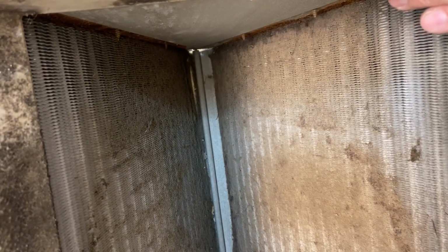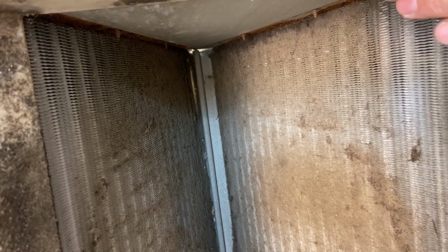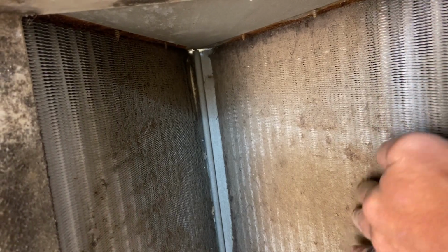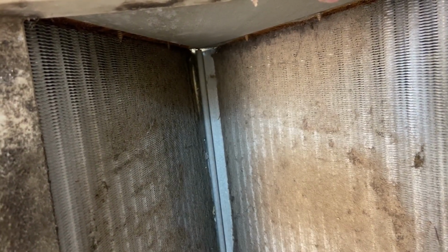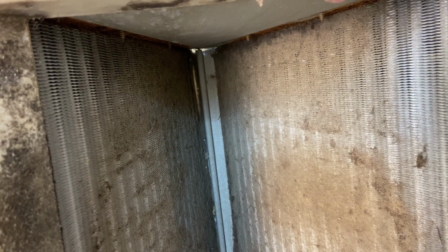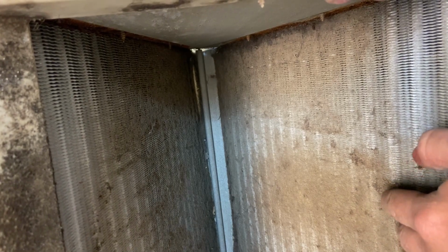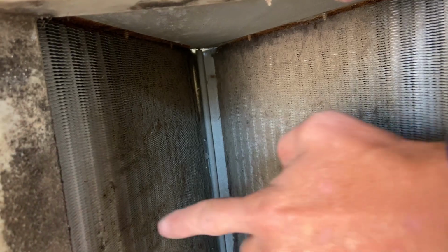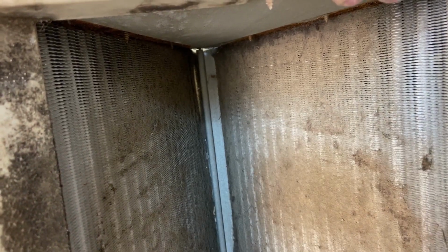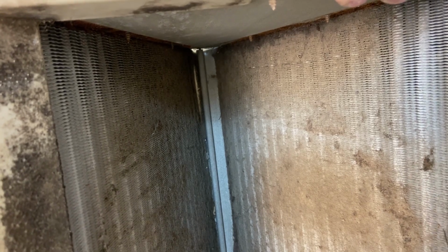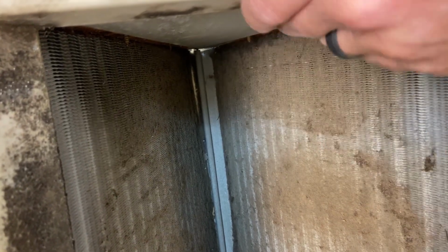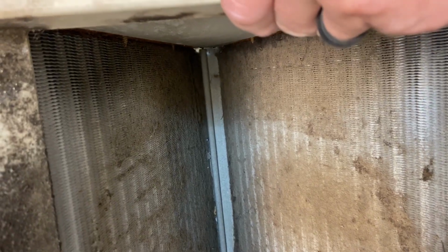Here's an example of an evaporator coil on the underside that's extremely dirty. This does 2 problems. Number 1, it's blocking airflow. Number 2, the dirt is working as an insulator. So insulators prevent heat transfer. It slows the second law of thermodynamics. So now I'm blocking airflow, so that means there's less heat coming across it. And also with the dirt, I'm insulating the coil, so I'm slowing the heat transfer down. This makes this evaporator coil less effective. I'm not transferring heat from the air to the refrigerant like we need to, and it's a very big problem. So airflow is essential.